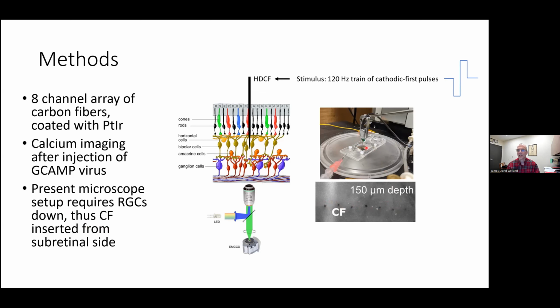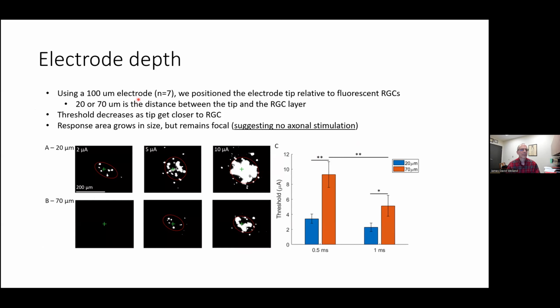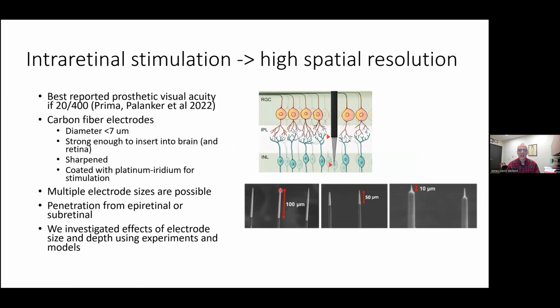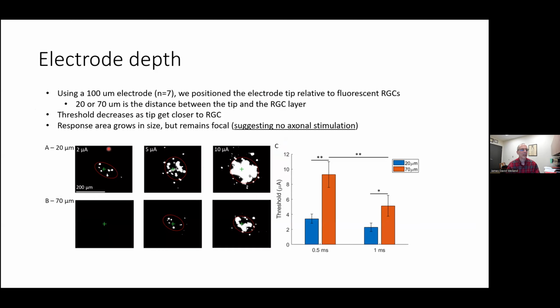There's a mouse retina in this dish. You really can't see it, but this is the holder for the carbon fiber array. So using these electrodes, we had a 100 micron electrode. What I mean by that is that the exposed length of the electrode is 100 microns. So that's what that term means. We're able to show that when we have the electrode tip 20 microns from the retinal ganglion cell layer, we get a response with 2 microamps of current, which is quite low. And it increases in a way that suggests we're not activating axons, though I will say in some cases in this position, we did see axonal activation. At 70 micron distance, it requires more current in order to generate similar responses. So this is the measurement of the threshold, and we show that by being closer to the retinal ganglion cells, you achieve lower threshold.